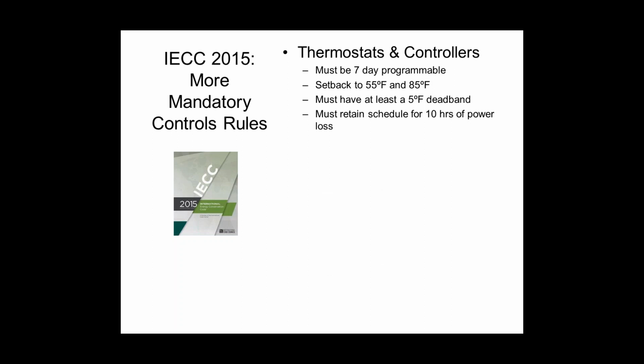You got to retain the schedule for 10 hours of power loss. You could do that with a battery backup, but quite honestly, that's stupid. So don't do that. You're better off, any modern thermostat has a double EEPROM chip in it, so it burns the settings in there. And if you lose power, it doesn't go away. But if you really want batteries, God bless you, put batteries in.